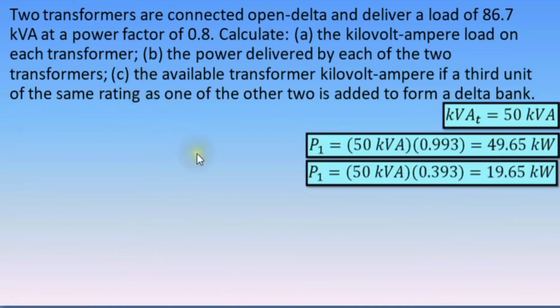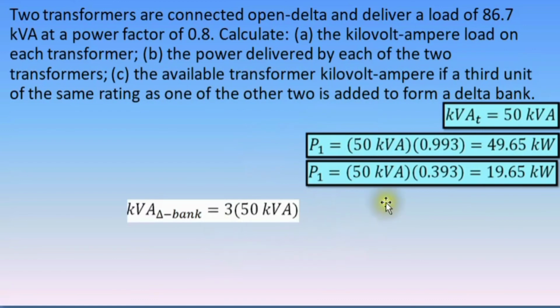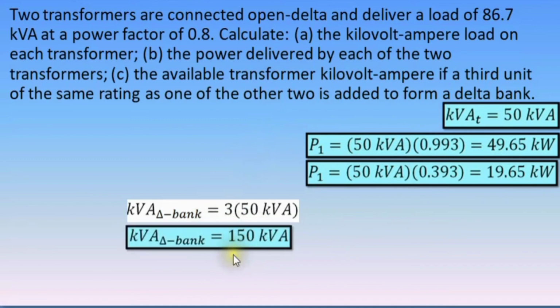And now for letter C, calculate the available transformer kilovolt ampere if a third unit of the same rating as one of the other two is added to form a delta bank. That is simply multiplying the rating of each transformer, that is 50 kVA, by 3. So 3 times 50 kVA, that is 150 kVA.